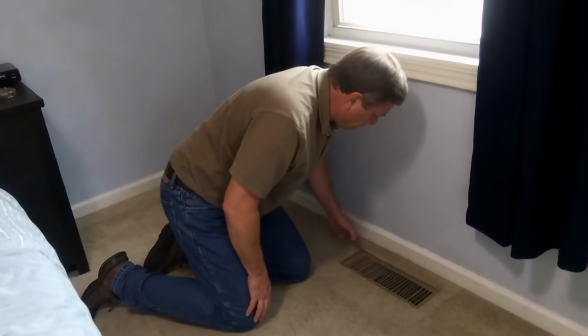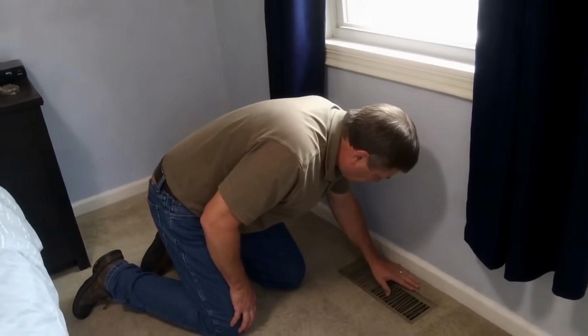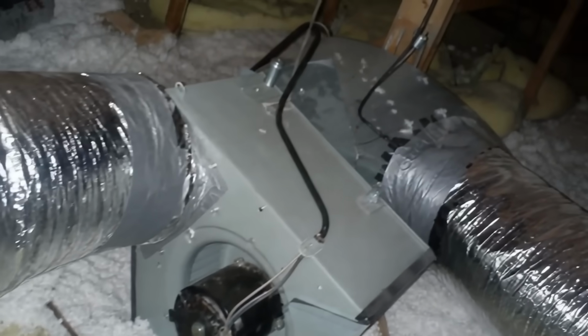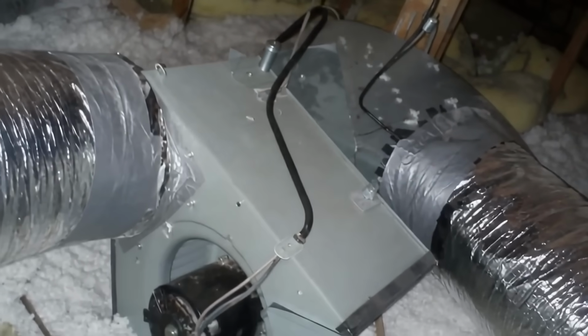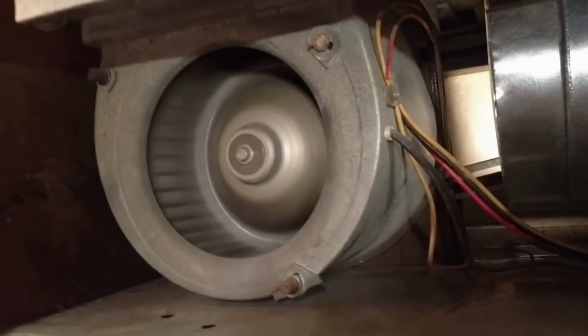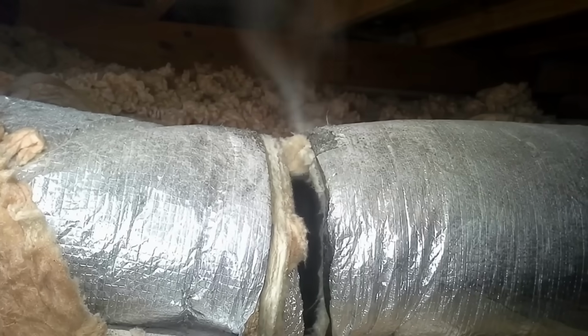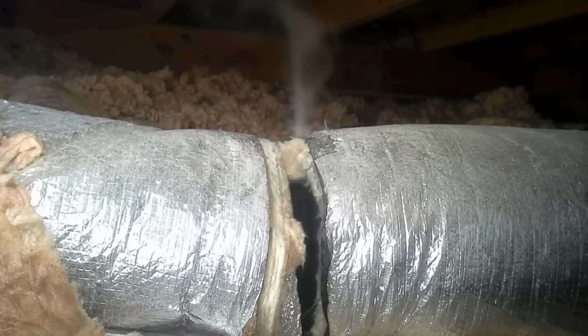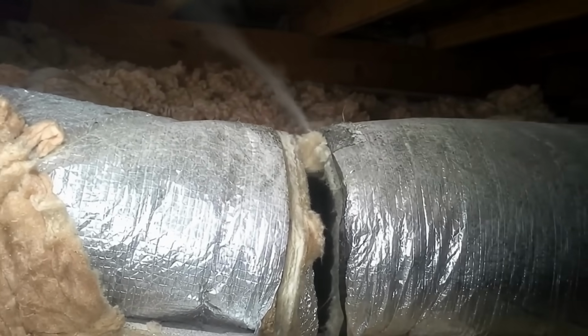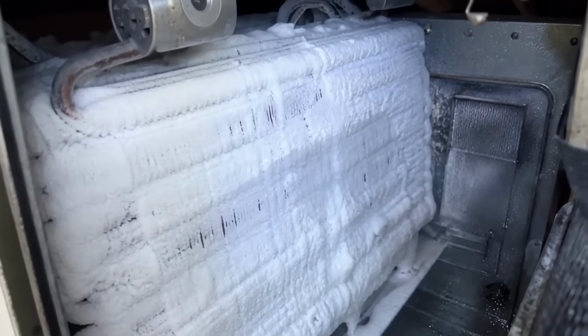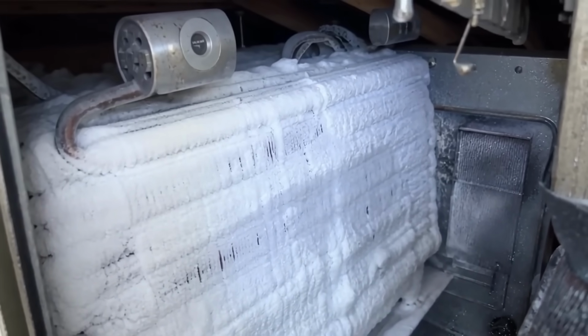When you close a vent and you don't redirect that air, you build a wall. The air's got nowhere to go, so the pressure backs up in the ductwork, and now your blower motor is straining against something it was never built to push on. That pressure hunts down the weak seams in your ducts and blows your cooled air straight into the attic. It can starve the airflow across your indoor coil so badly the thing freezes into a solid block of ice and shuts you down completely.